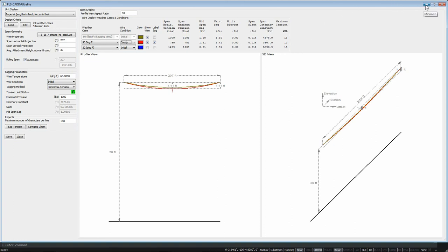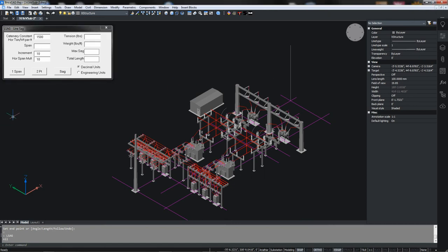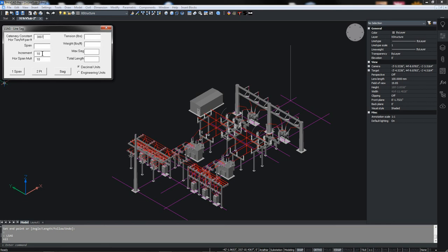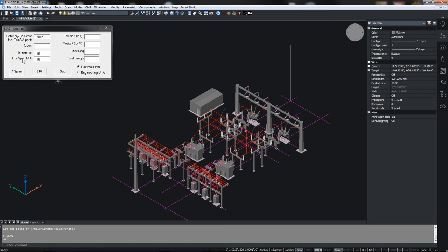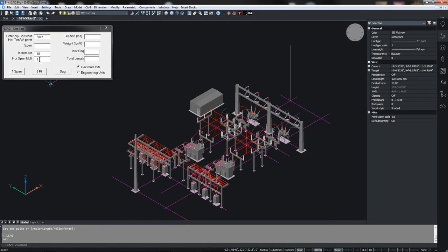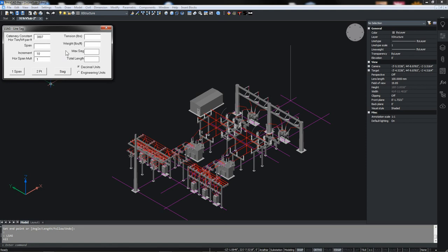Let's go back over to our sag program and that's where we want to put in our catenary constant 3807. Now if we were doing a single span sag we would put in a span. The increment here is the increment along this sag curve for each polyline segment. The horizontal span multiplier usually on a transmission line you're using a 10 to 1 multiplier for this span horizontal to vertical span. If you don't have this number, if you've got the tension, the horizontal tension and the weight or the load in pounds per foot, you can put this in here and it will calculate the catenary constant. These two values are calculated once we do the calculation.